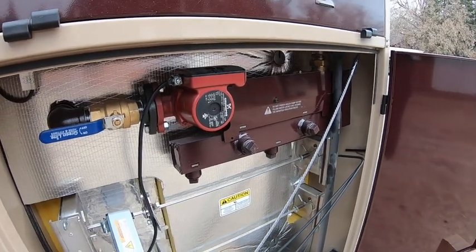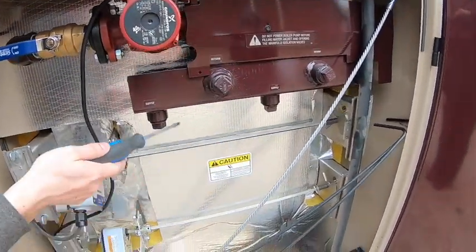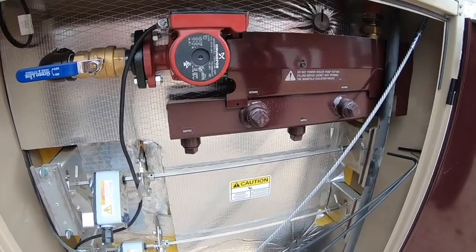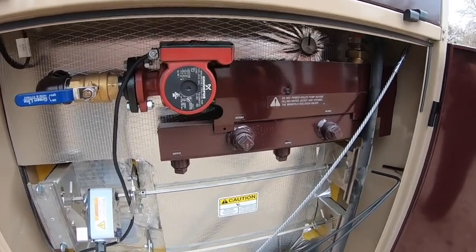When you were talking about that before, there's a mixer on the back, or how is it? It's a mixing valve and a boiler protection valve. That protection valve allows it to keep the water inside the cycle until the water's hot enough in the jacket to mix it off where it hits the right temperature.